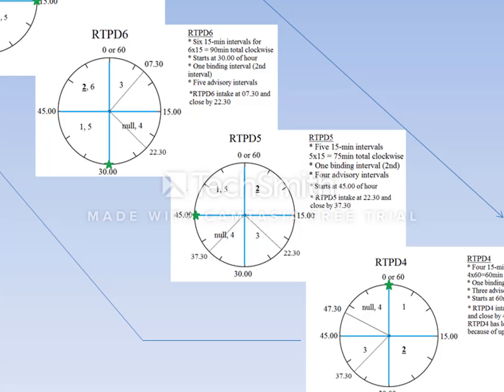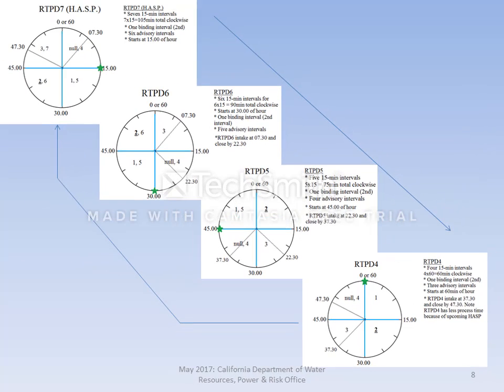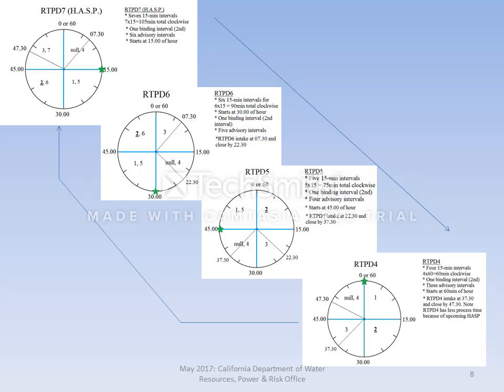PD5 samples inputs at the 22:30 mark of the hour. During the following few minutes but no later than the 37:30 mark, PD5 performs an iterative computation to identify the most optimal feasible unit commitment solution. At no later than the 37:30 mark, the unit commitment decision published as five 15-minute market results is made available individually to generation units through ADS and globally through OASIS. PD5 produces five 15-minute intervals for 75 minutes total. PD5 instructions commence at the 45-minute mark, and only the second 15-minute interval — between the zero and 15-minute marks of the next hour — is binding. Intervals 3 through 5 are advisory.